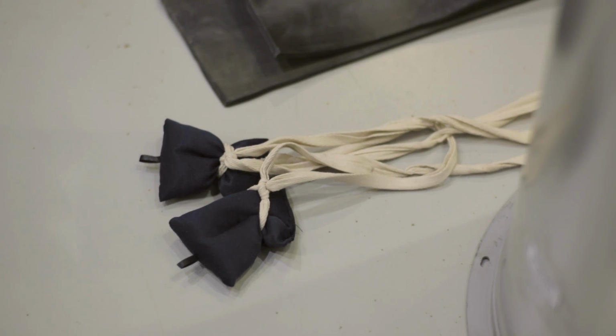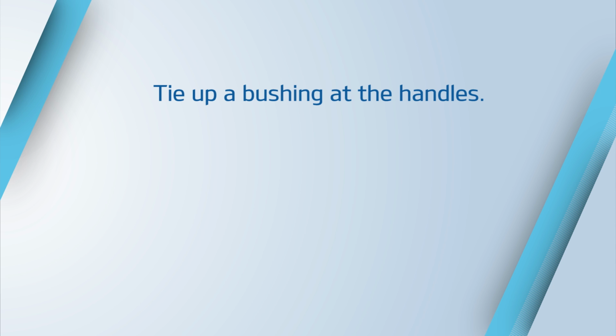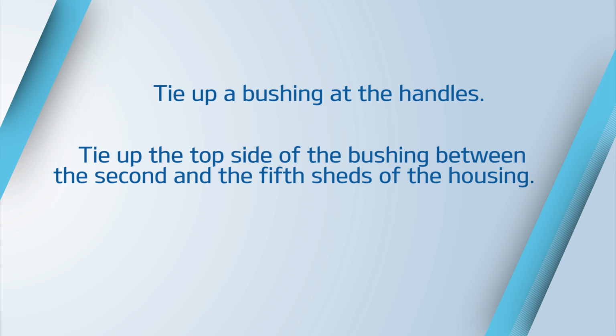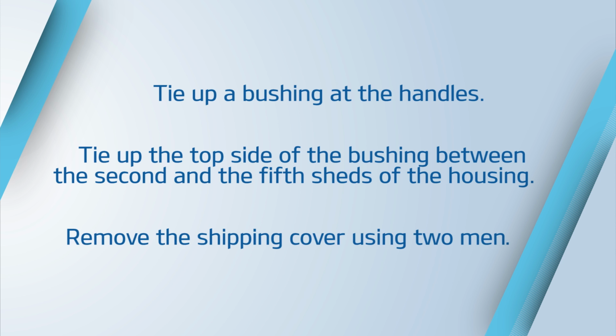Thus we have had a look at the bushing removal and unpacking. Let us now go through the key steps again. Tie up a bushing at the handles. Tie up the top side of the bushing between the second and the fifth sheds of the housing. Remove the shipping cover using 2 men.